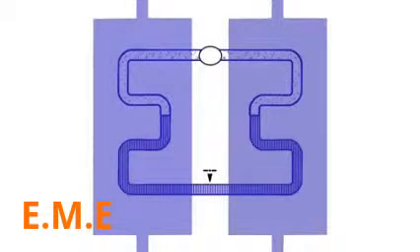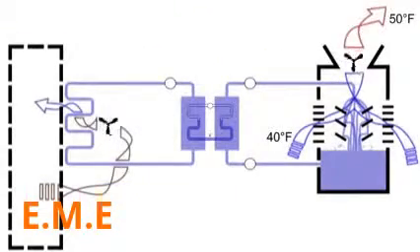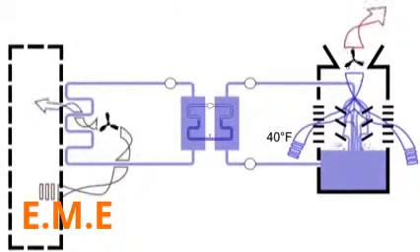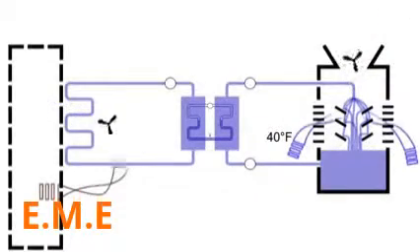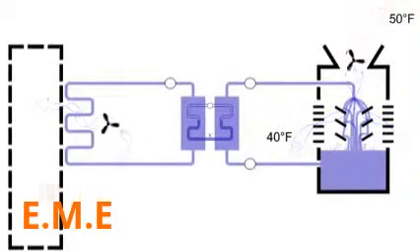The expansion valve opens, and this is important. The cooled coolant moves to the evaporator without fighting its way through the expansion valve, and there in the evaporator, it cools the chilled water. We bypassed the compression refrigeration process entirely and still created chilled water for delivery in the standard way.